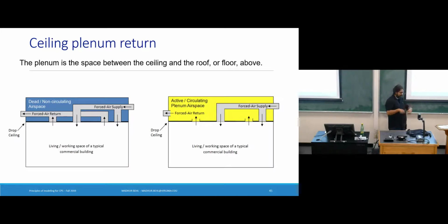So to think about it again, we are getting cool air into the zone. The cool air is taking the heat out of the zone. This heat is being generated by us as the hot water bottles, and so this return air now is at a higher temperature. Some of this return air is going to get circulated back along with the outside air as well. So essentially what has happened is, the heat in the air of this room or this zone has been transferred into this air handling unit loop.